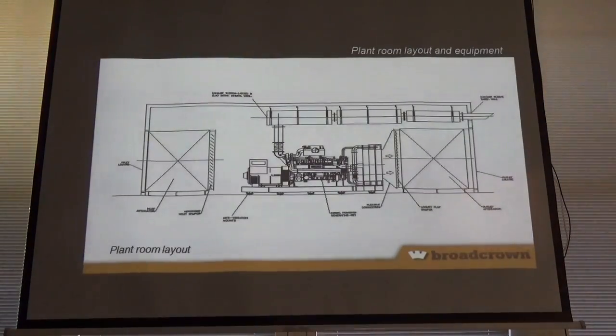This is a plant room. Normally they like putting it in the sub-basement, which makes it fun. That set mounted full push radiator for the KTA38 G5 will give you 11.2 metres cubed, or require 11.2 metres cubed per second of cooling air. Combustion air is 1.123 metres cubed per second. So basically that's the summation of those two being drawn in at the inlet here.